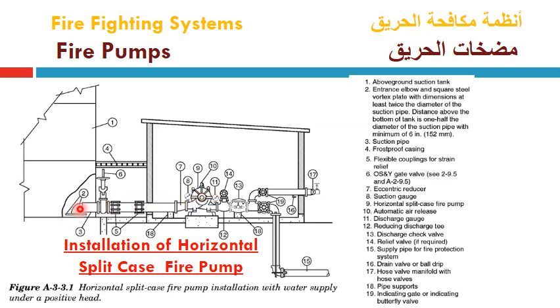Then number 2, the entrance elbow and square vortex plate to prevent vortex motion on the suction side. Then number 3, suction pipe. Number 4, frost proof casing to prevent this valve chamber from ice in cold areas. Then number 5, flexible coupling for strain relief between the fire pump room and the tank and the valve chamber, to take any strain which may happen during installation or operation or sudden stoppage of the pump.